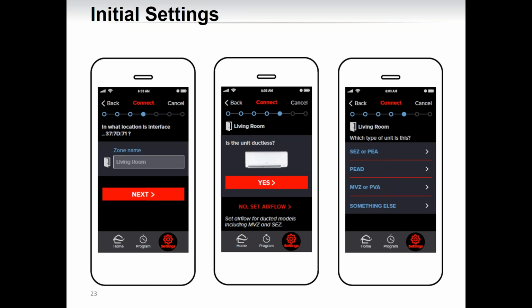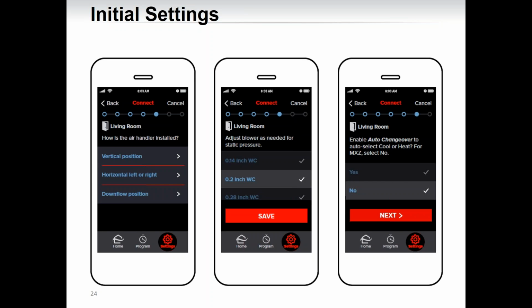For an indoor unit with advanced function features, like external static on an SEZ, you'll be able to specify if it's installed vertically, horizontally, or downflow on an MVZ, and then set the appropriate external static settings based on the ductwork installed.